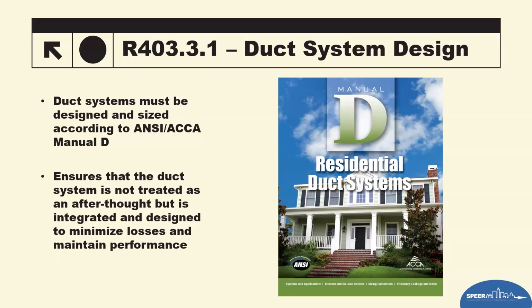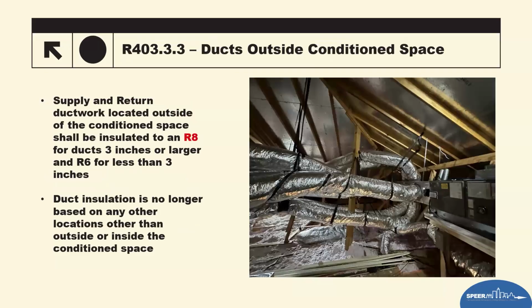There's software out there that makes it super simple and easy to do. It is a little bit time consuming, but it's going to show proper airflow and proper duct sizes. You could, as a building official or a third party, walk out on site, look at the duct design in Manual D and say, well, that's supposed to be an 8-inch, and I'm looking at a 6-inch. That's wrong. And that's where we'll start calling it out by saying the duct design is not installed per the Manual D that's been turned in for permit.